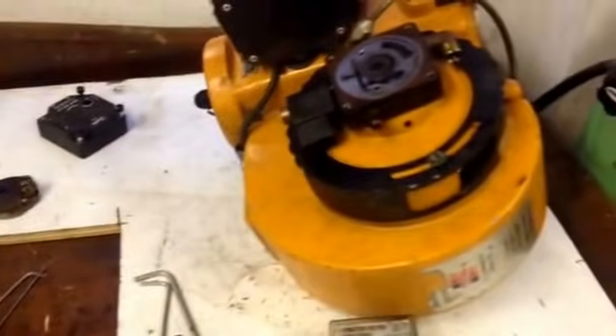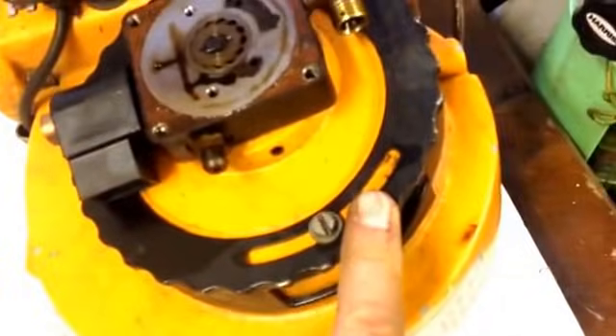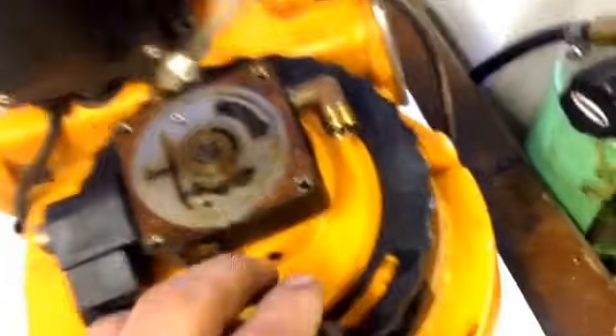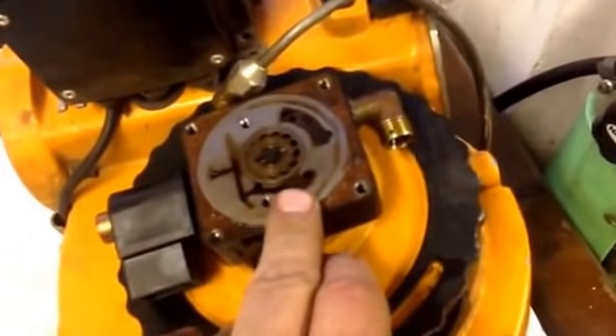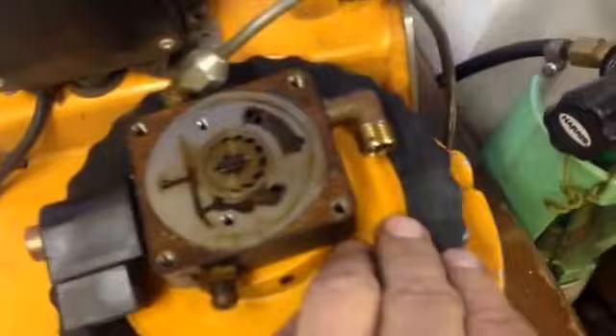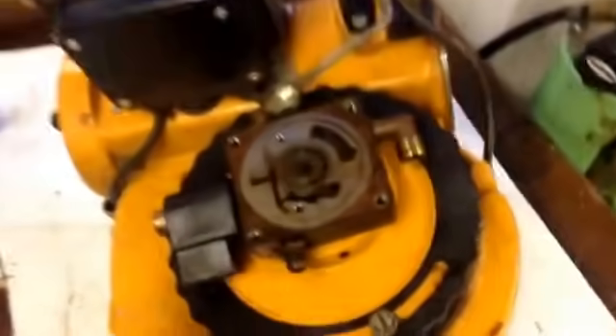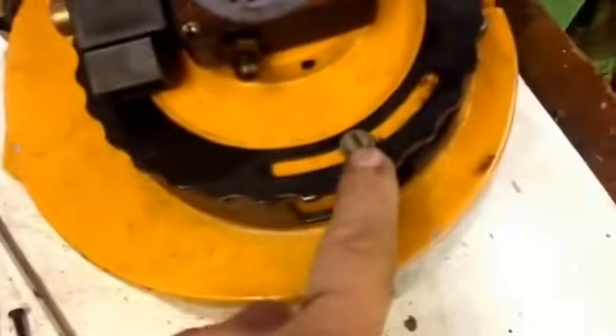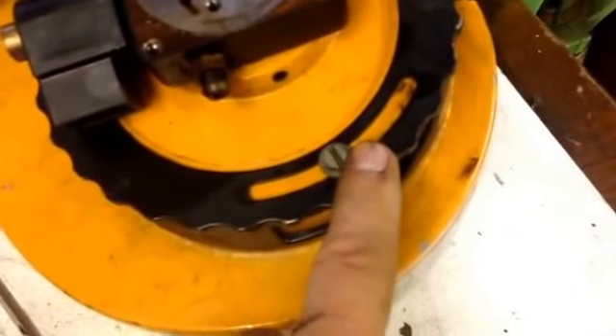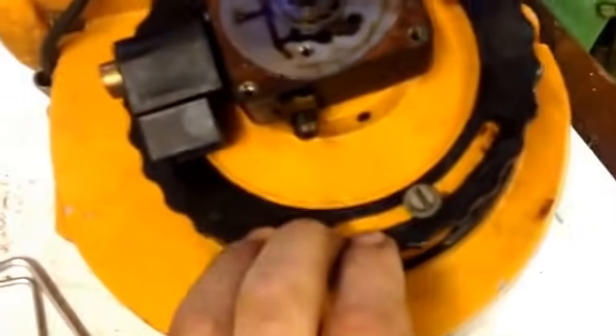There's no real way of being able to see visually how well these things are burning. So if you've got a flue gas analyzer, you can start to tweak the air mixture, raising or lowering the air. The thing to do is set the oil pressure to the manufacturer's rated amount first. This one hasn't actually got a plate telling you what the pressure should be, but most will have a plate that says set me at 140 psi or whatever. Start with that and then work with the air, because that's your easiest way of doing it.